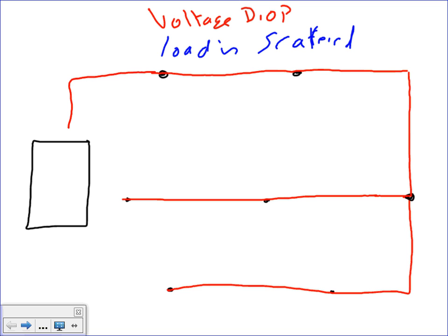We came all the way and we fed it from a 20 amp circuit. We have a 20 amp circuit that's moving all the way and feeding these lighting fixtures in a parking lot. Does anybody have any issue with that? Seven parking lot lights that we need to feed from this system, 20 amp circuit. The voltage, let's establish the voltage. The voltage is 120 at the source.